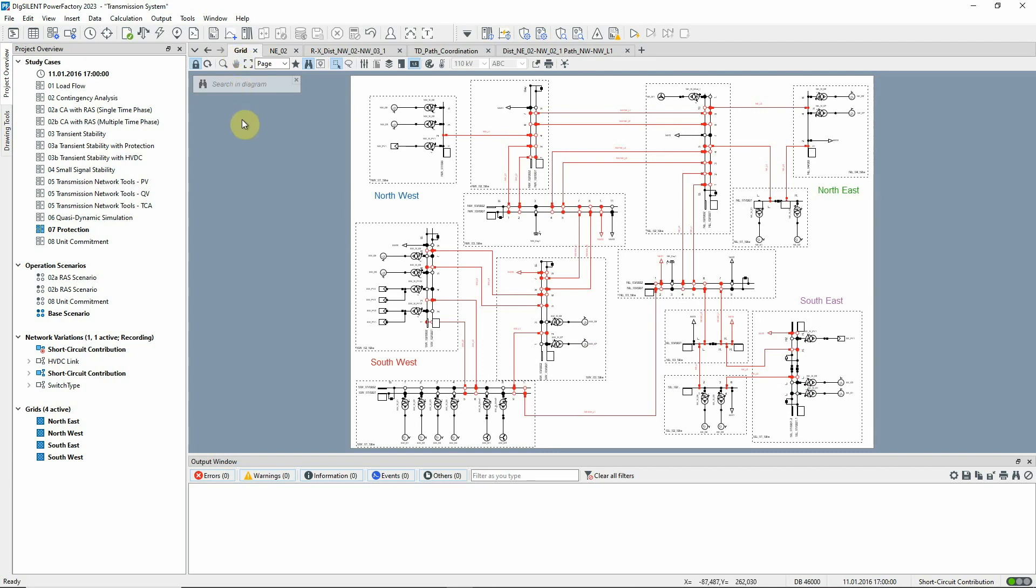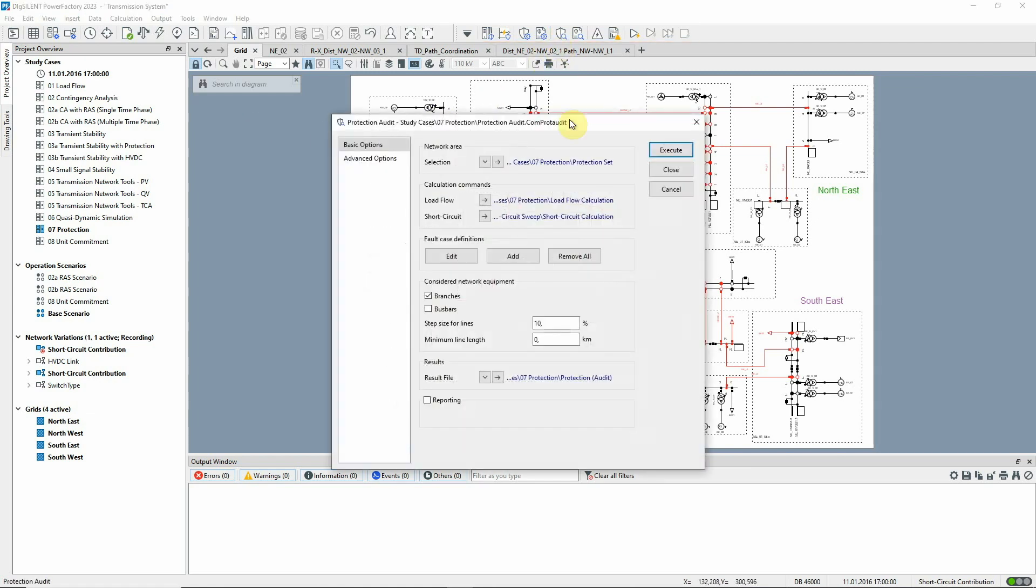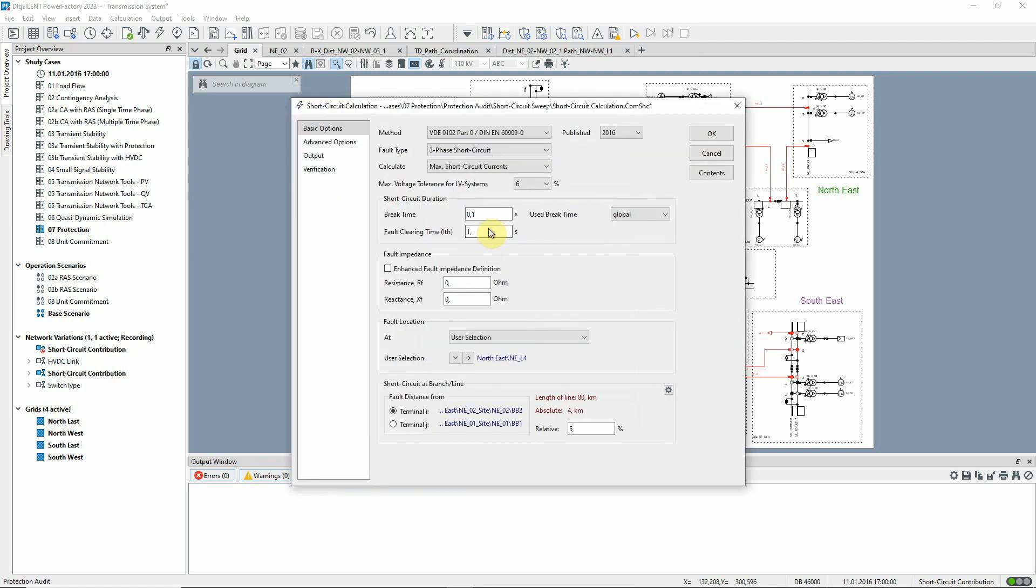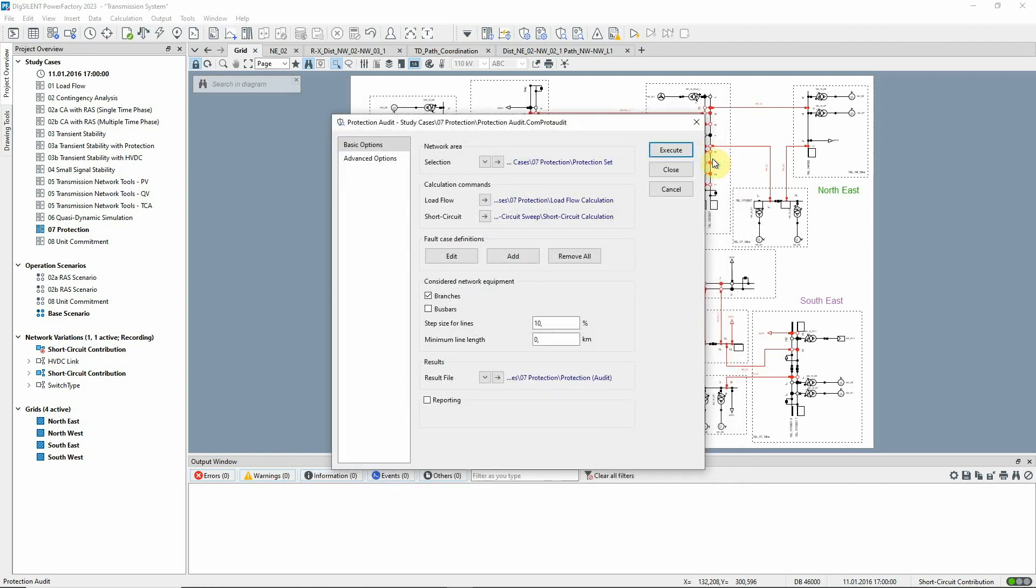We would now like to evaluate the protection scheme for different fault types. This is done using the Protection Audit tool which is found in the Protection and Arc Flash Analysis Toolbox. Here we can select the area where the short circuits are going to be calculated. This link gives access to the short circuit command to be used and the various fault types to be examined can be defined here.